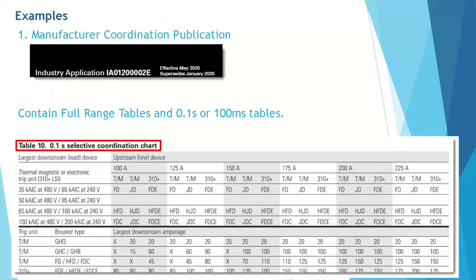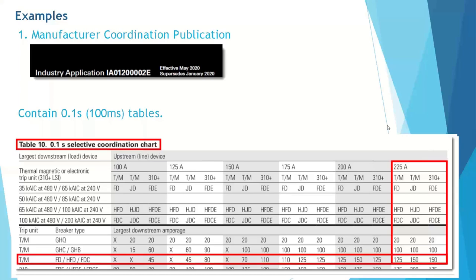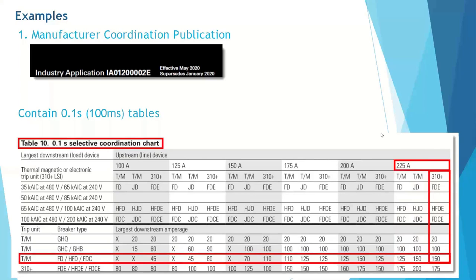Most people out there have been doing coordination for a long time know that the instantaneous bands often overlap. With the recent testing that all of these manufacturers have done to update their tables, they will say that even though you may appear to see an instantaneous overlap, the tested combinations are valid up to the current values specified in those tables. So for this example, we will be using Eaton's publication. I wanted to point out that there are two sets of tables in the publications typically. There are both full range and 100 millisecond tables.